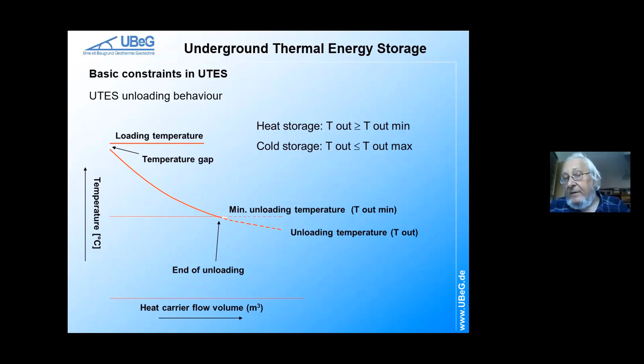By the way, there have been in the last years some attempts to use phase change materials in borehole heat exchangers, in fillings for borehole heat exchangers, for instance, to somehow remediate that. But the amount that would be required for actually seeing some effect is much too high to be practically used in any way.